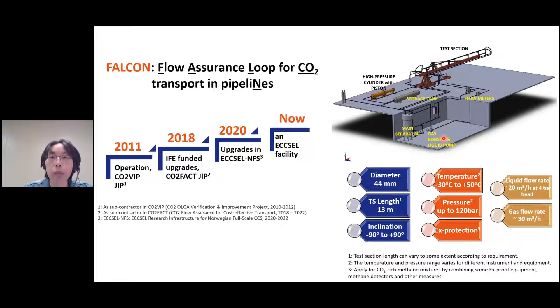The loop is also equipped with advanced instruments to measure different parameters for different tests. For the flow loop, of course, the flow meters are quite important to measure the flow rate. We have Coriolis meters and also sonic meters. The loop is equipped with many temperature sensors and pressure sensors. Also, we have an online system to sample and analyze the impurities in the CO₂ stream. This is a GC instrument, and this is the laser spectrometer. At the moment, we can measure impurities of nitrogen, methane, water, and oxygen. Of course, the system can also be expanded to other impurities.